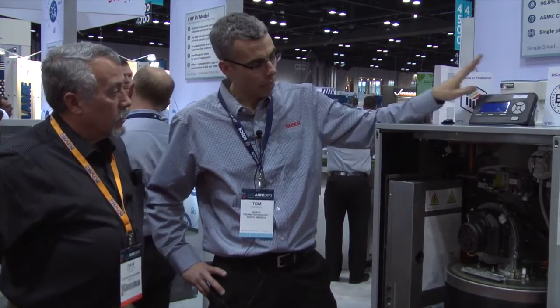of the boiler here, we have our exhaust and our air intake adapters. This is typically where you would have to put on an appliance adapter if you were going to use more of a polypropylene or PVC or CPVC or even stainless. You'd need to apply an adapter to then use that pipe. What we've built into this product is a very unique step-down adapter set, so that any of those pipe materials can fit in here without any appliance adapter. So this will speed up and make the installation go a lot smoother for the contractor.